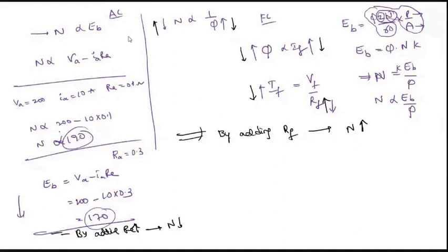Sure. So remember, while performing our machines lab experiment, always the motor field rheostat will be kept at minimum position, to maintain the minimum speed at starting condition. If the field rheostat is mistakenly kept at the maximum position, obviously the machine will run at dangerous speeds. Sometimes the machine will even come out from the plinth. That is one of the drawbacks of keeping the field rheostat at maximum. So that's why the motor field rheostat is always in minimum position, whereas in the case of a generator, it will be maximum.